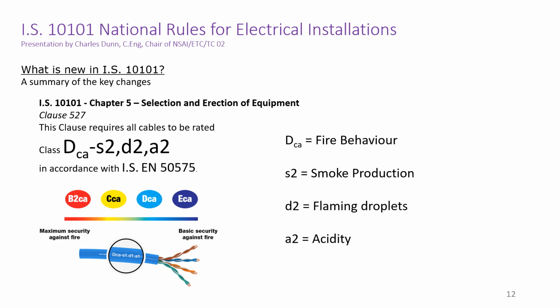Well, the core of the rule is to define and improve the classification of cables with regard to their response to fire. Experience has shown that cables in the fixed wiring installation present a risk when a building is on fire. Cables are often installed above the escape route. Depending on the duration or intensity of the fire, cables can obstruct the escape route with smoke or poisonous fumes. We are familiar with low smoke or zero halogen cables, but how low is the smoke and how close to zero is the halogen risk?